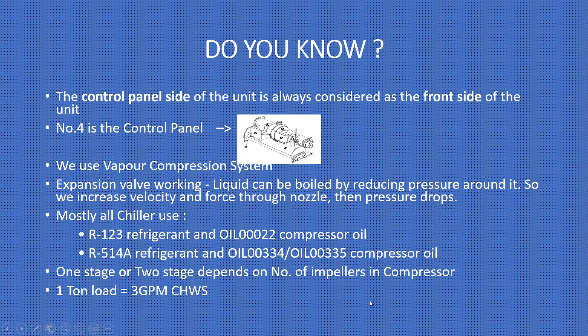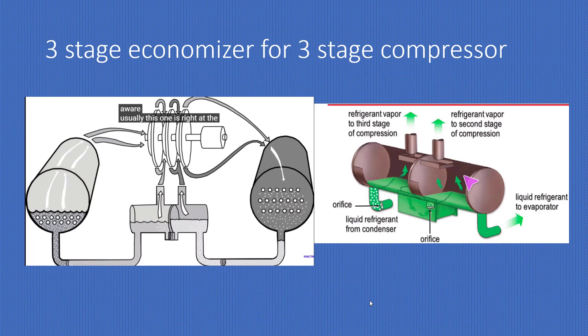The control panel side of the unit is always considered the front side. We use a vapor compression system — expansion: working liquid can be boiled by reducing pressure around it, so we increase velocity and force through a nozzle, then pressure drops. Most of these chillers use R123 refrigerant and oil 00022 compressor oil; in some cases R514A refrigerant is used with its corresponding compressor oil. Whether one-stage or two-stage depends on the number of impellers in the compressor and the load. Three GPM chilled water flow is the measurement for one ton of cooling load. For a three-stage compressor, the economizer will also have three stages — you can see one, two, and three stages here with orifices; liquid refrigerant from the condenser goes inside the economizer and refrigerant vapor goes to the second stage of the compressor.